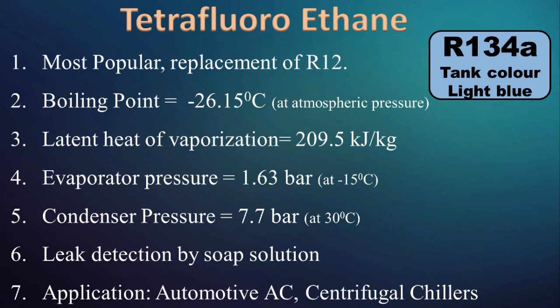R134A, Tetrafluoroethane, is the most popular refrigerant in AC and refrigerators. It is a replacement for R12 since it does not affect the ozone layer. It has a boiling point of minus 26.15 degree Celsius, with evaporator pressure of 1.63 bar and condensing pressure of 7.7 bar. Leak detection of R134A can be done by soap solution. Applications of R134A include automotive AC, centrifugal chillers, and many more.